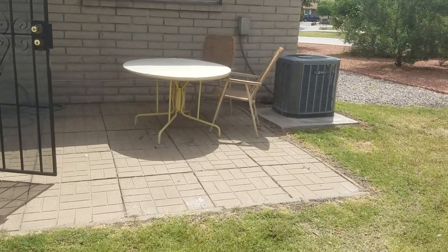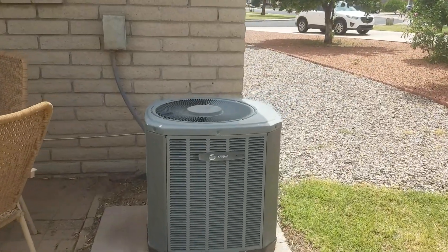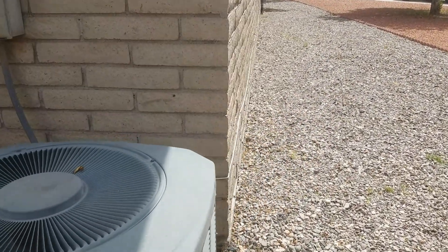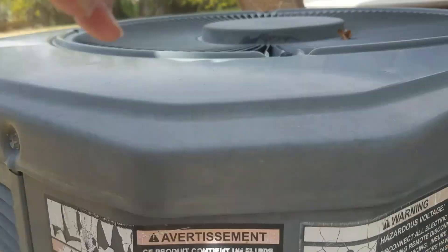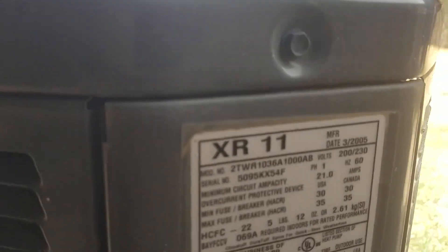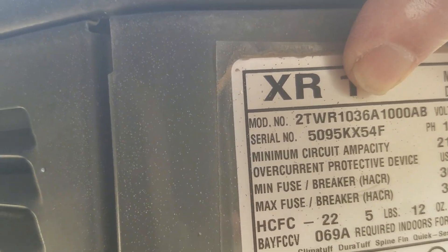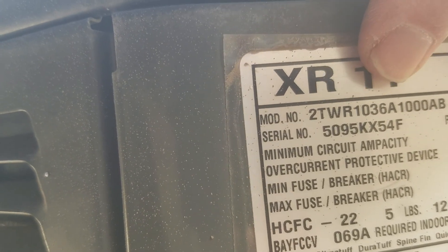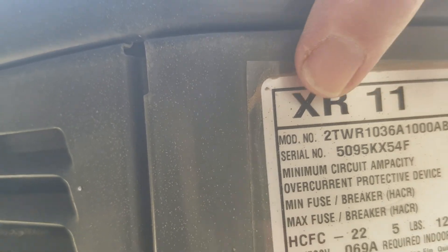What's the AC? There's kind of a pet negative of this big room — you don't really have a patio. Trane AC — doesn't look brand new. Model number: TRW 36. See the 36 — divide by 12: 12, 24, 36 — that's a three-ton unit. Because 12 goes into 36 three times; that's what the code is in the model number for the tonnage.